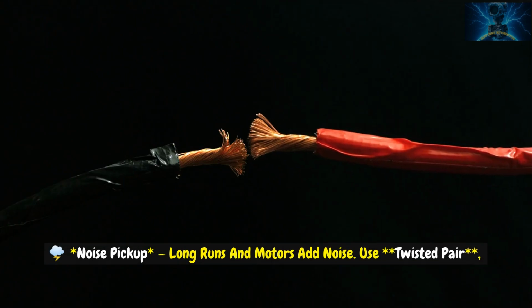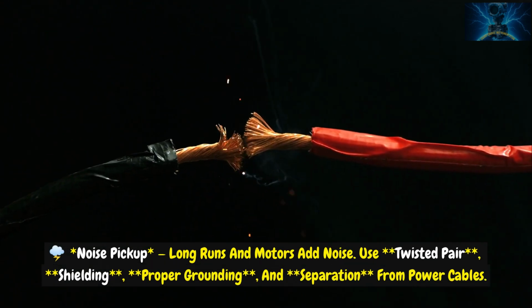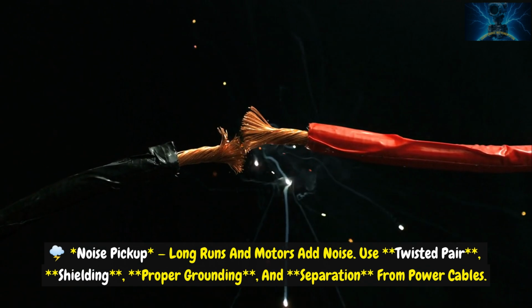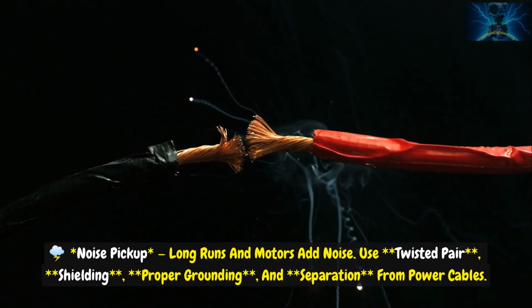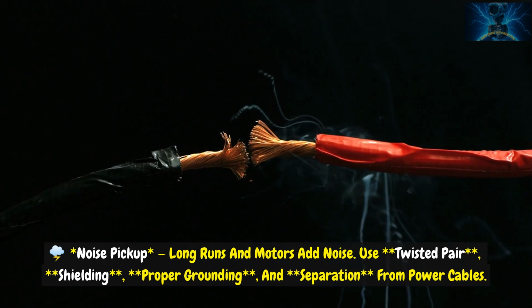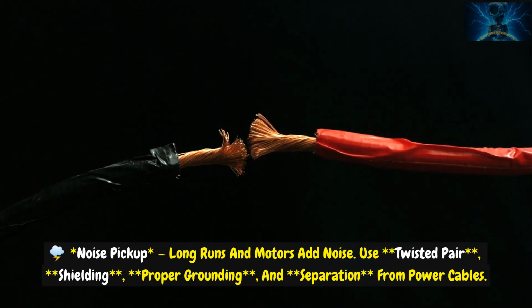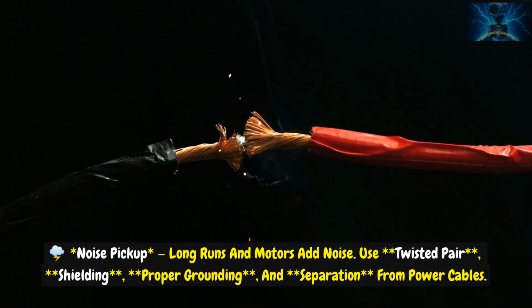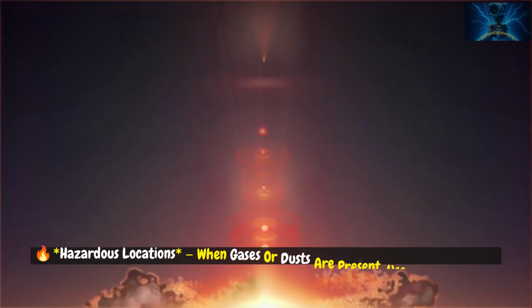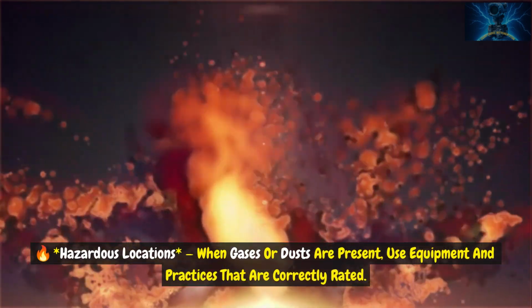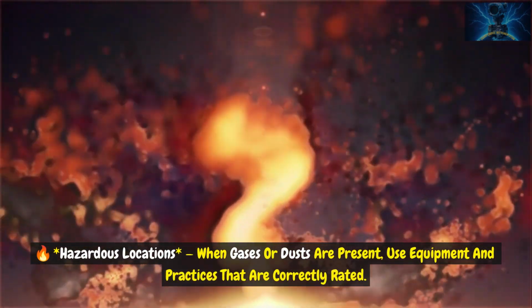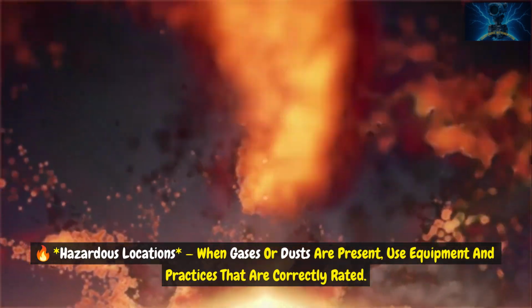Noise pickup. Long runs and motors add noise. Use twisted pair, shielding, proper grounding, and separation from power cables. Hazardous locations. When gases or dusts are present, use equipment and practices that are correctly rated.